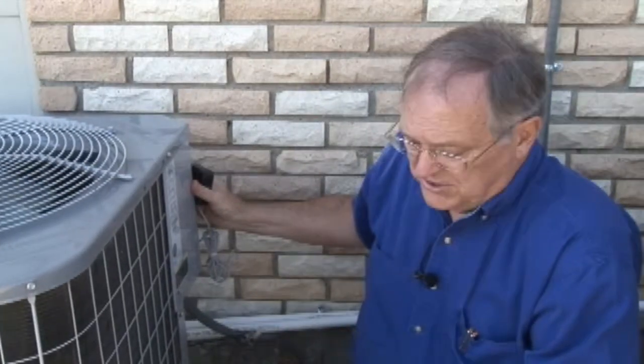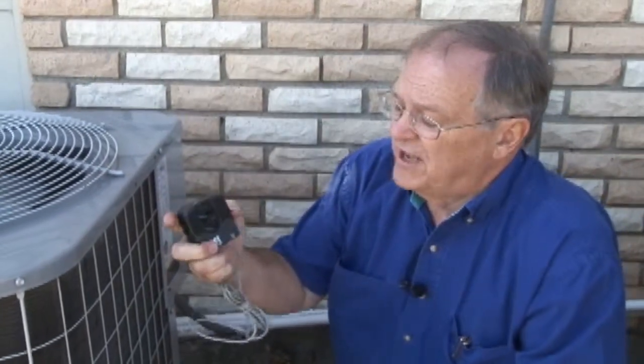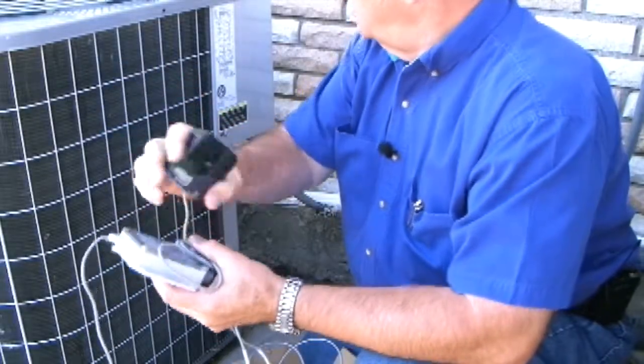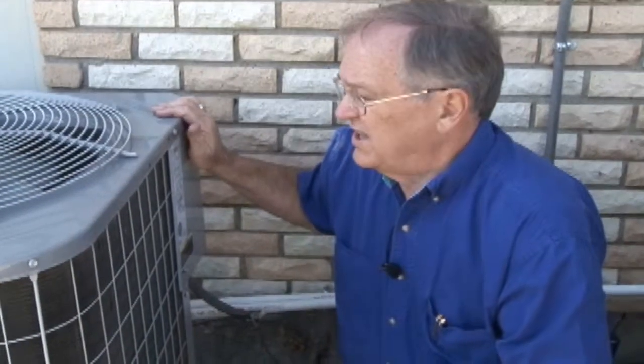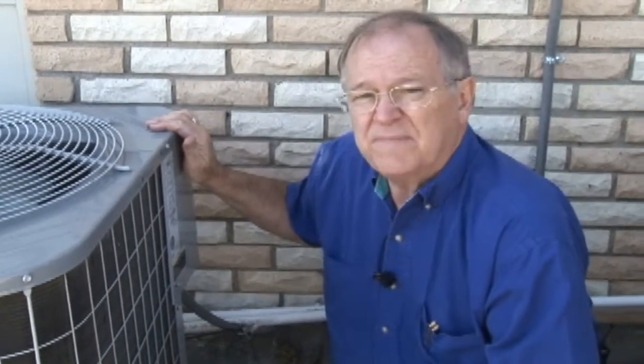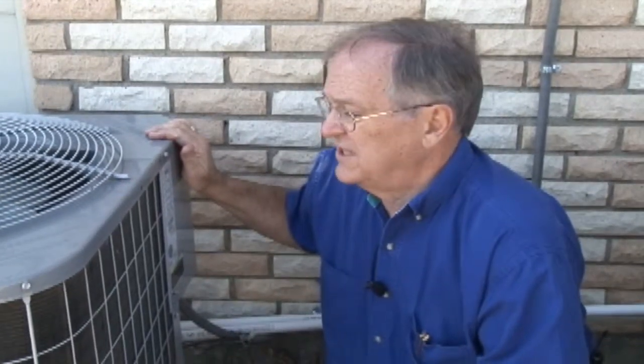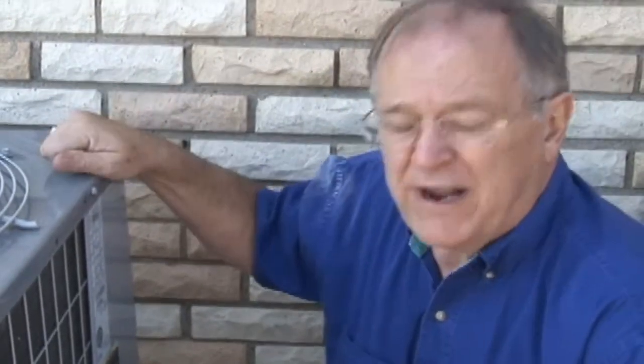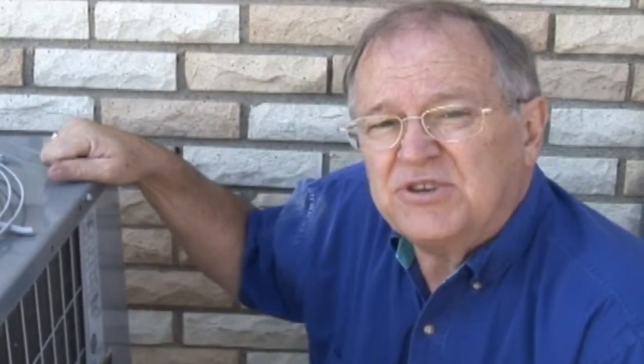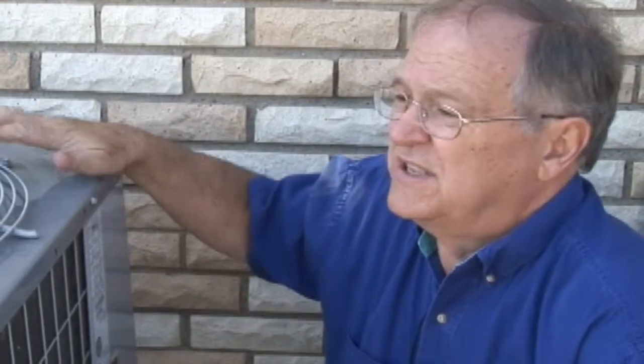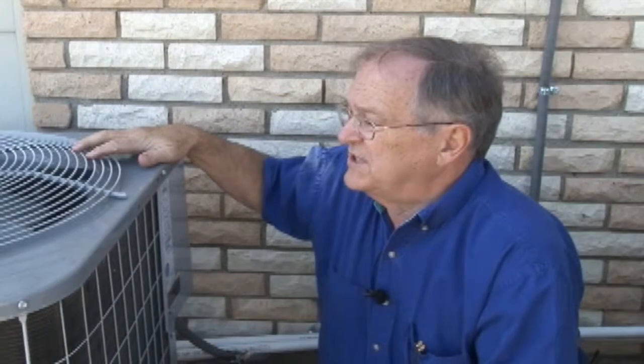Typically, we'll pull off this inspection panel, attach the Amp probe on L1, and, being very careful to wind the wires around the data logger, we'll put this inside this system here to measure the baseline for a week. Then we'll come back, and using the laptop computer, we'll download the data that we've collected, and at the same time we'll export the data into the Excel spreadsheet so that we can examine the data and make sure that it's exactly what we want before we treat this system with Ice Cold. Because once the system is treated, you can never get baseline information again.